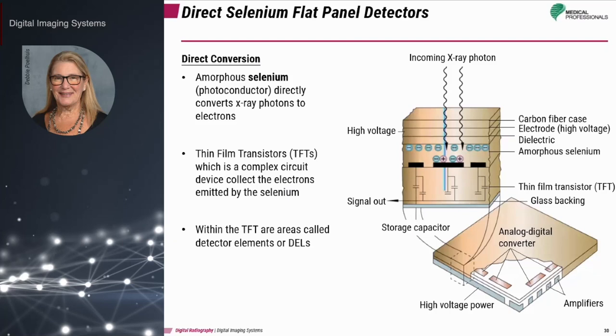Photoconductors are materials that absorb X-rays and immediately convert them into electrons, which are collected and stored by the thin film transistor array. Incident X-ray photons interact with the amorphous selenium and create electron holes through direct ionization of the selenium. The electrical charges are in proportion to the amount of X-ray exposure received. The charges are collected in a storage capacitor in the TFT and remain there until readout by the switching action of the TFT.